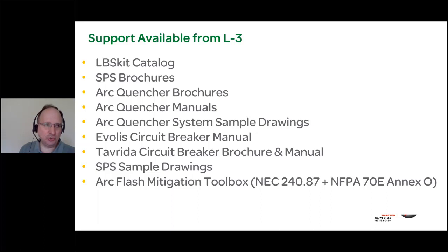And we also have a one-page document you can request from your L3 representative. We call it the Arc Flash Mitigation Toolbox. This lists every approved NEC 240.87 and NFPA 70E Annex O method, all in the same chart. We list every approved arc flash mitigation method, the mechanism by which it achieves arc flash mitigation, the approximate clearing time associated with that method, and then any advantages or disadvantages associated with that solution are summarized all in one nice document. So for anyone who's doing design taking arc flash and electrical safety into account, it's a great document to have as a reference design tool. Again, all of this is available from your L3 sales engineer.